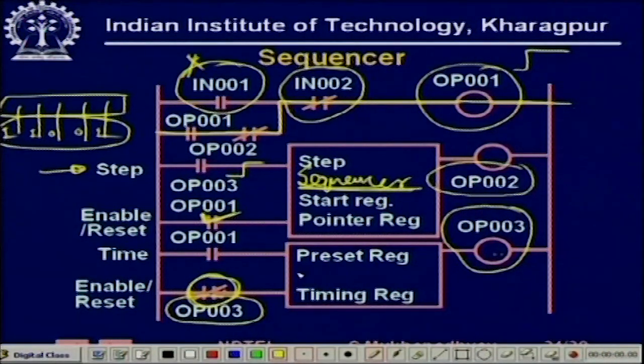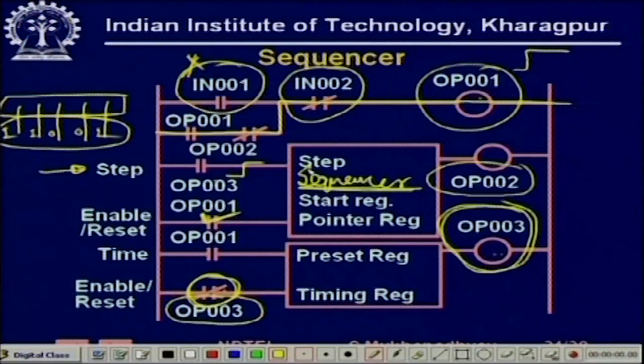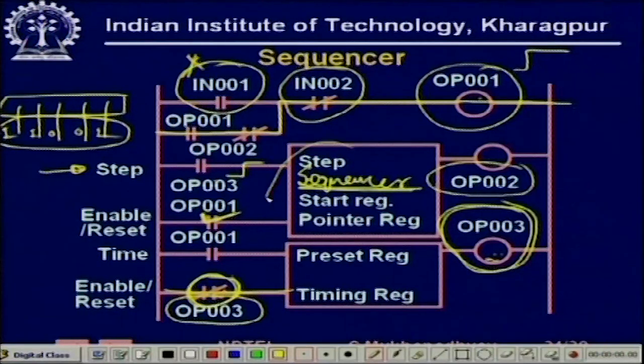OP001 is already on, so it times again. Basically this arrangement continuously times, and the moment OP003 goes high after the timing interval, it gives a pulse to the sequencer. A step is executed in the sequencer, then because it is latched, when this goes high it resets again, and once reset it starts timing again. So it continuously generates timing intervals and at the end of each interval a pulse executes the next sequence register of the sequencer.